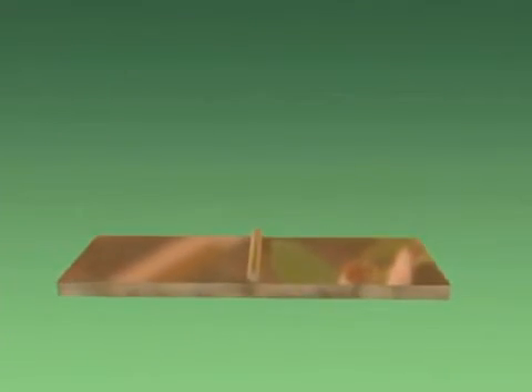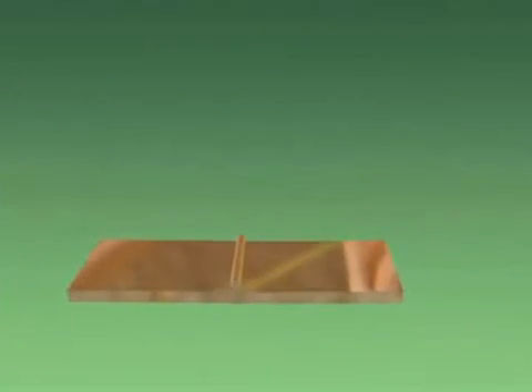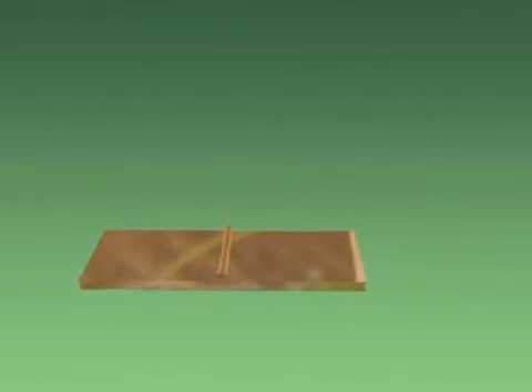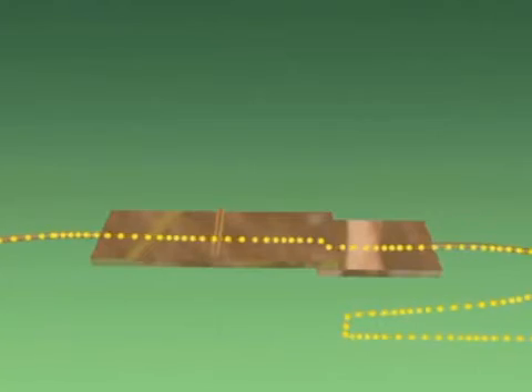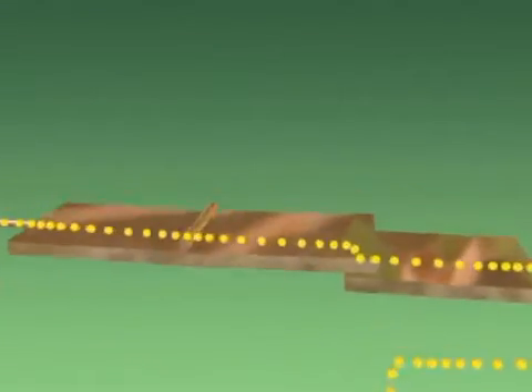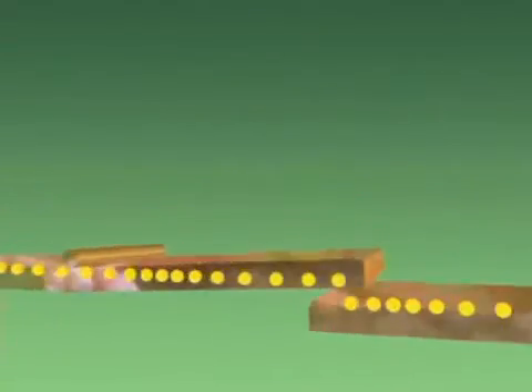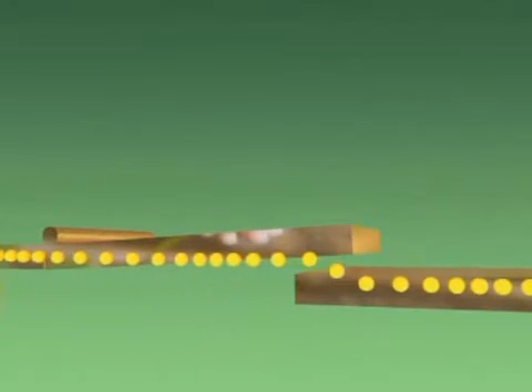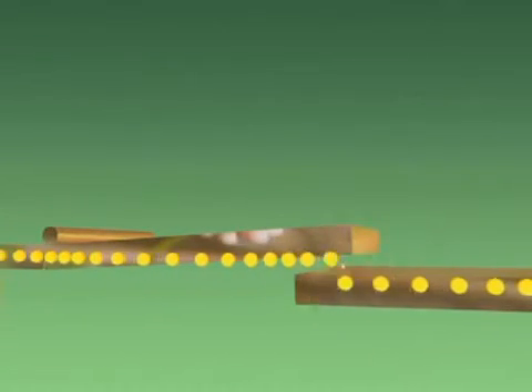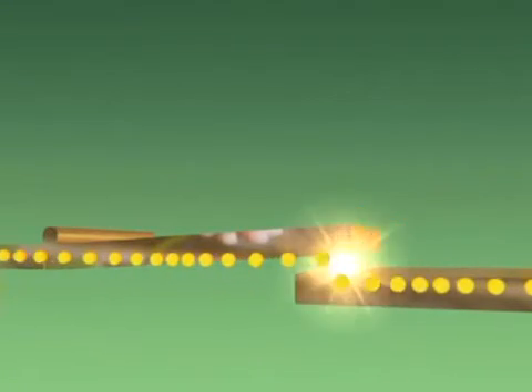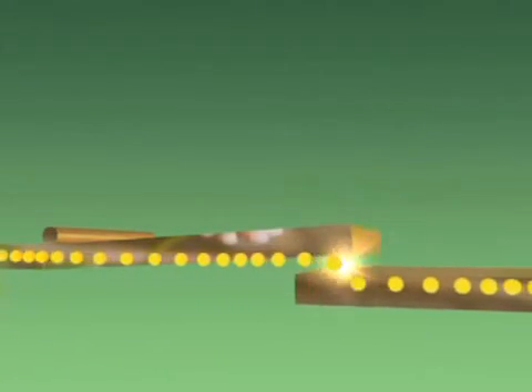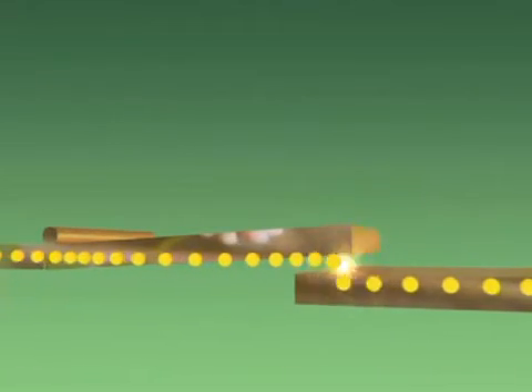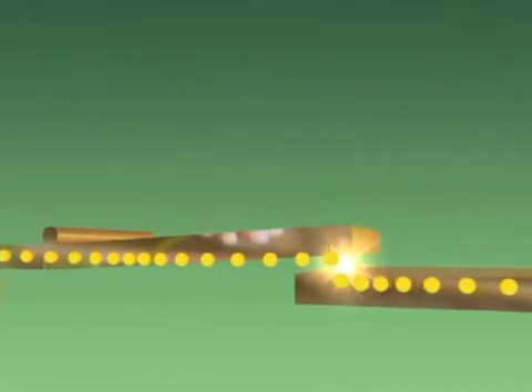At the heart of a circuit breaker is a simple switch which can open and close. When closed, a circuit is completed through the circuit breaker and current can flow. But almost open and almost closed switches leave a tiny gap of air, which current can bridge with an electric arc. This arcing damages the metal surfaces of the switch and shortens the life of the circuit breaker.